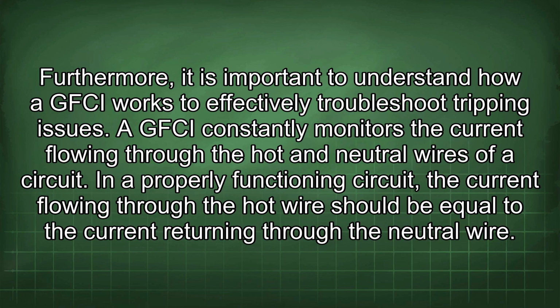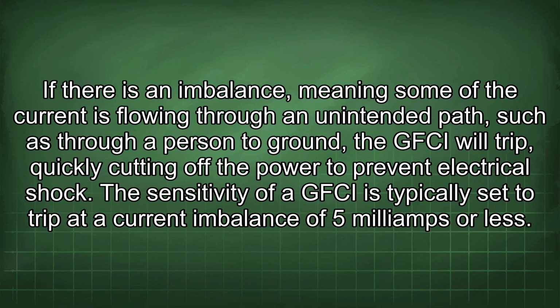A GFCI constantly monitors the current flowing through the hot and neutral wires of a circuit. In a properly functioning circuit, the current flowing through the hot wire should be equal to the current returning through the neutral wire. If there is an imbalance, meaning some of the current is flowing through an unintended path, such as through a person to ground, the GFCI will trip, quickly cutting off the power to prevent electrical shock.